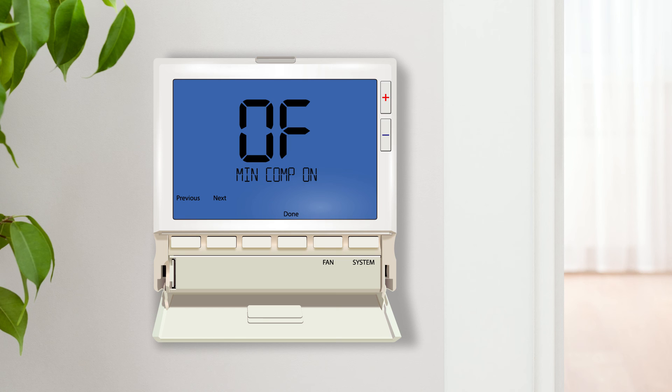Minimum compressor on time forces the compressor to run for a minimum of three to five minutes every time it is activated, regardless of the room temperature. This increases the efficiency and longevity of the outdoor unit.